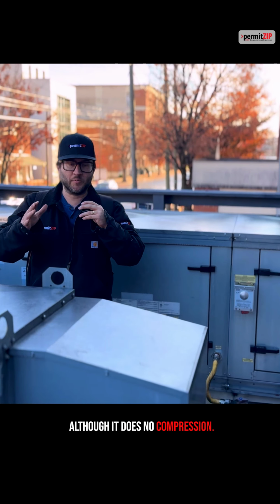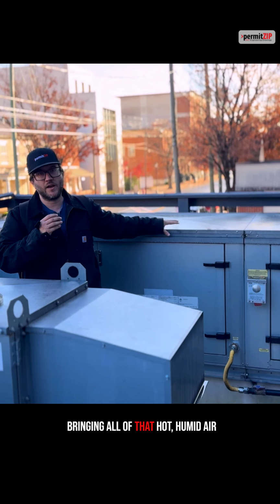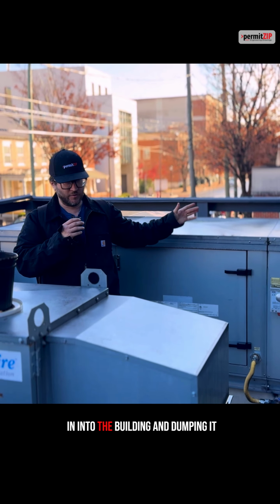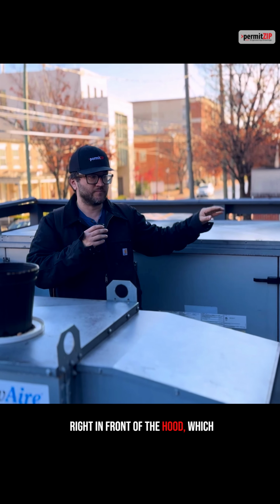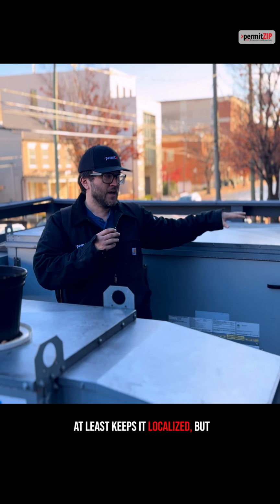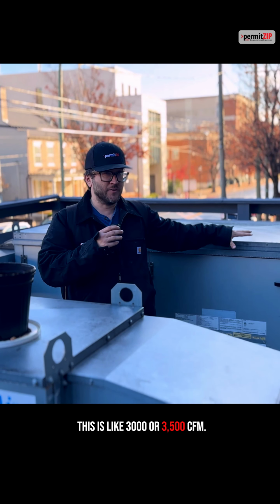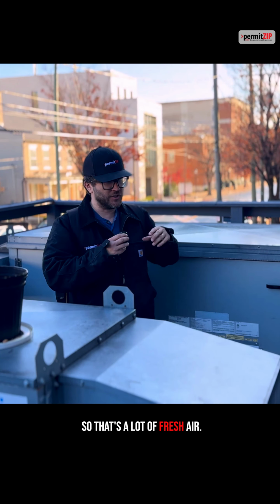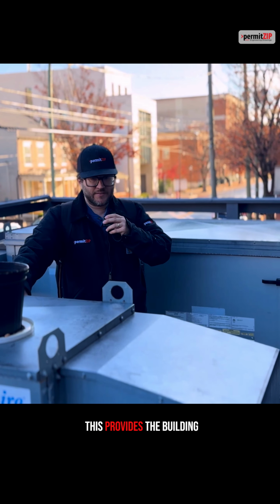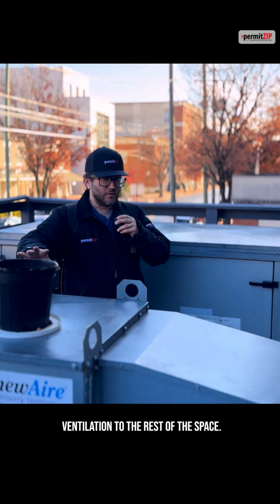it does no compression. So during the summer, we're bringing all of that hot, humid air in to the building and dumping it right in front of the hood, which at least keeps it localized. But this is like 3,000 or 3,500 CFM, so that's a lot of fresh air. This provides the building ventilation to the rest of the space.